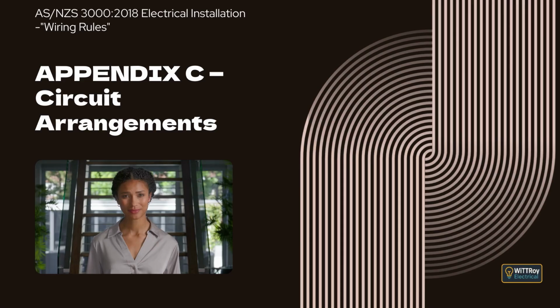Clause C 2.4.1, Method. This clause explains that load is allocated to different types of equipment connected to consumer mains or submains in a non-domestic installation. The load current is calculated for each equipment load group in the installation, or in the affected part of the installation, and the individual contributions are then added together to obtain the maximum demand. The accompanying guidance clarifies how different load types are treated and how the calculations are carried out in practice.